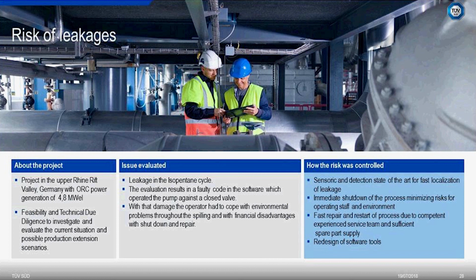As we detected on site in a visual inspection of the power plant and within the documentation the investor and the operator gave us, we found a leakage problem in the isopentane cycle, which had occurred a couple of months before our visit.